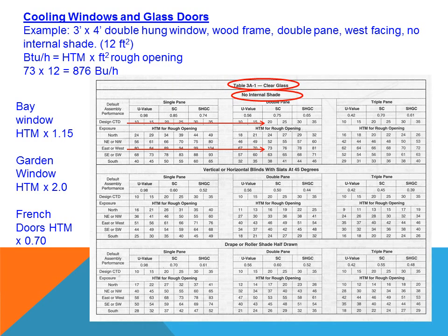Here is a simple example: we have a 3x4 double hung window with a wood frame, double pane, facing west, with no internal shading — which is 12 square feet (3 times 4). We fill in the information and to figure out the number of BTUs, we take the square feet and multiply it times the heat transfer factor. Looking at the chart, it's facing west with a temperature difference TD of 20 — 95 degrees outside and 75 degrees inside. Following that down, we get 73. That one window of only 12 square feet will transmit 876 BTUs per hour.